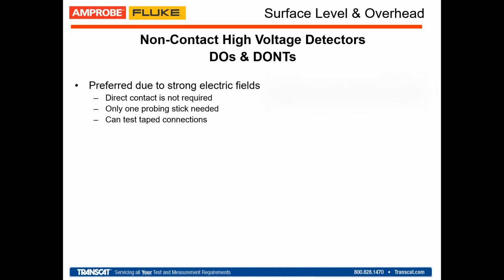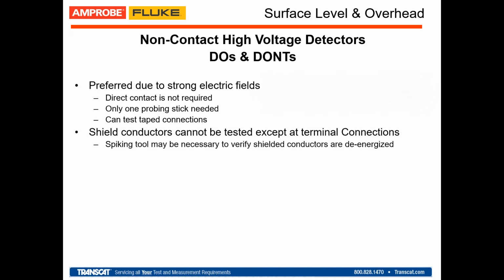And there's always a hesitation from end users to take that approach because they're just not comfortable making contact with anything above 220 volts or going above 1 kV, right? So that's one of the main benefits of the non-contact high voltage detectors. You do not make contact with the hot line. Now, unfortunately, they don't work, as with most non-contact technologies, when the cables are shielded or have some kind of jacket that isolates or entraps the electromagnetic field. So if you want to detect voltage on a shielded high voltage energized cable, you need to go straight to the naked terminal where you can see the conductor to detect voltage or not.